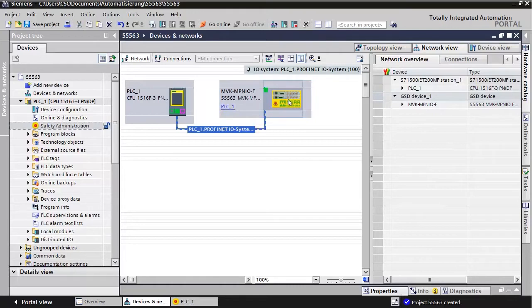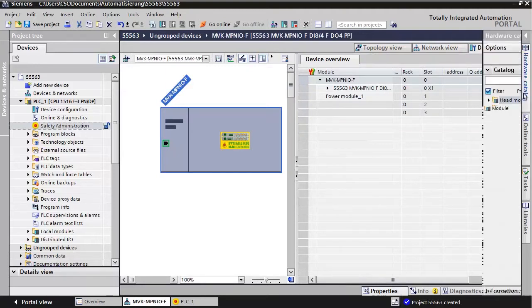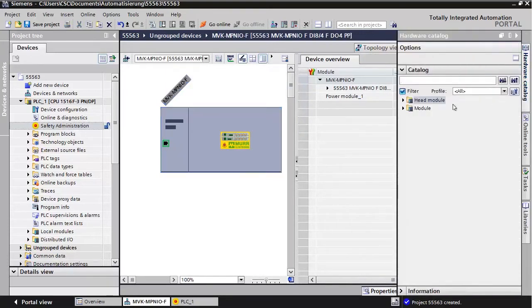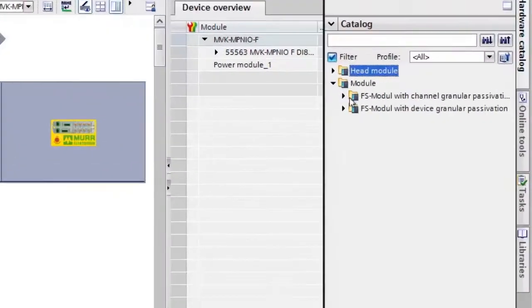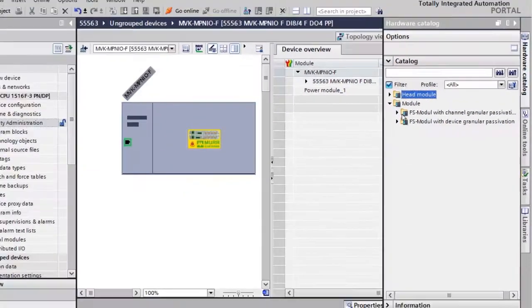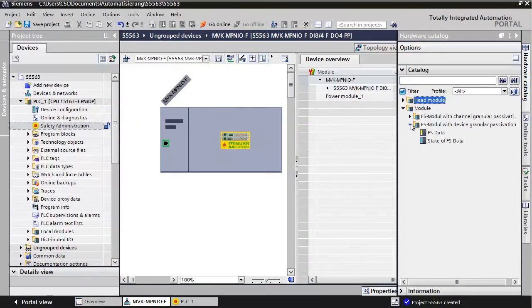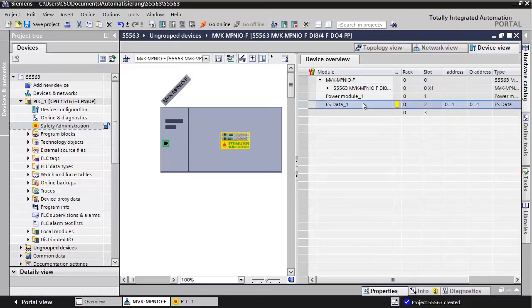Double-click on the MVK module icon. There are two ways to work with the module: Device granular or Channel granular passivation. In this tutorial, we will use Device granular passivation. That means that in case of any fault, the whole module will be passivated, not just the affected channel. For this, insert the FS Data module located in the folder FS Module with Device granular passivation.